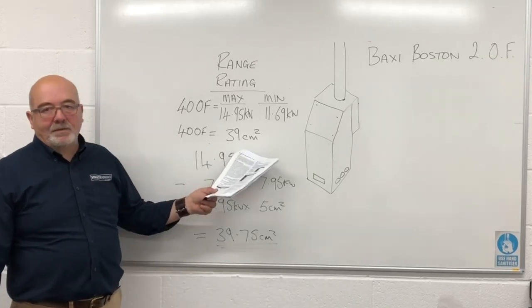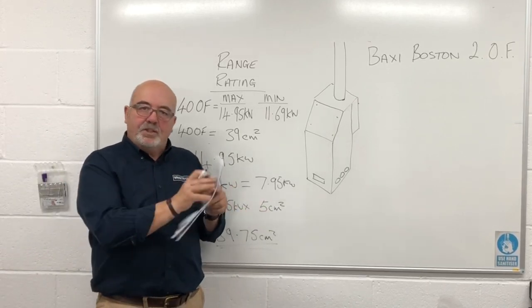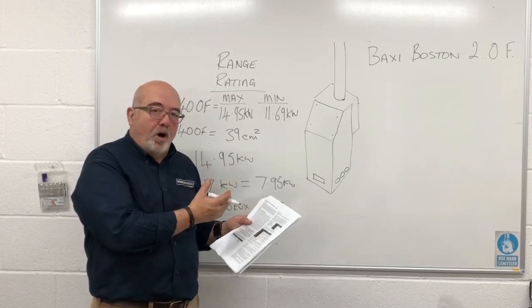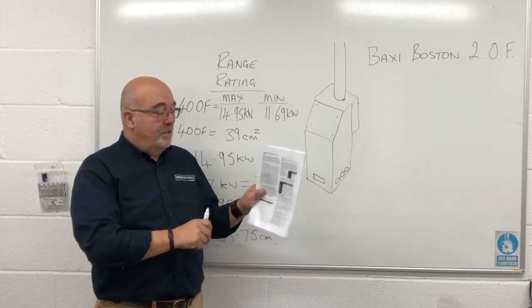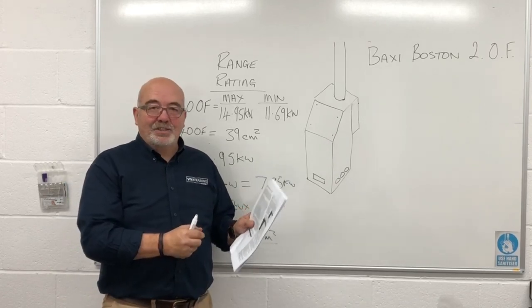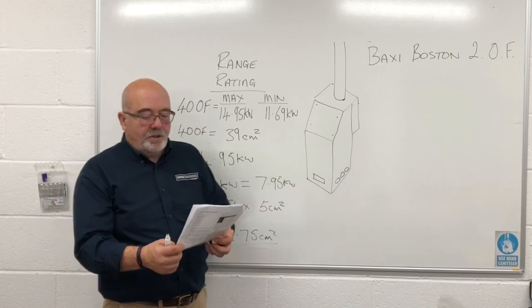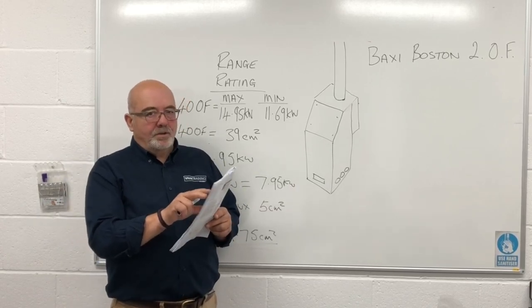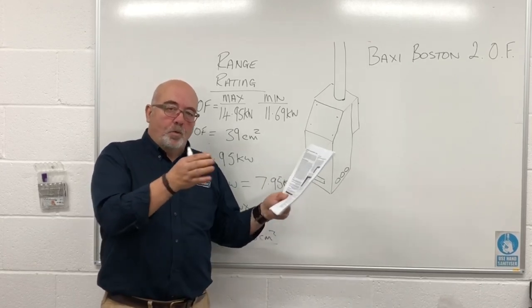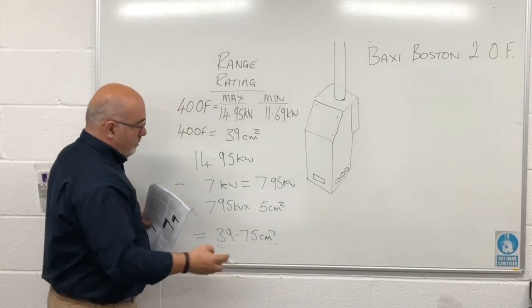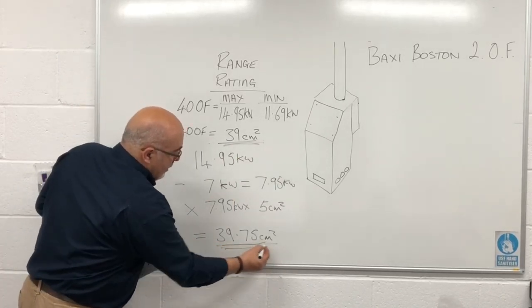So: 7.95 kW multiplied by 5 cm² per kW gives us 39.75 cm² — and the manufacturer's instructions state 39 cm². That proves the point. When you're on a job looking at ventilation and you've got something that tells you what it should be, just get your phone out and calculate it — input minus 7 kW, multiplied by 5. You should come out approximately to the answer in the book.